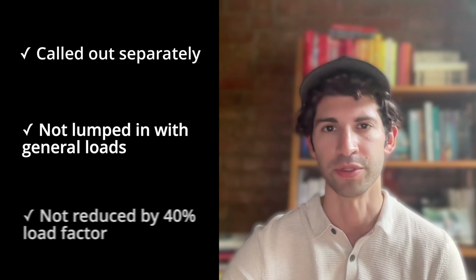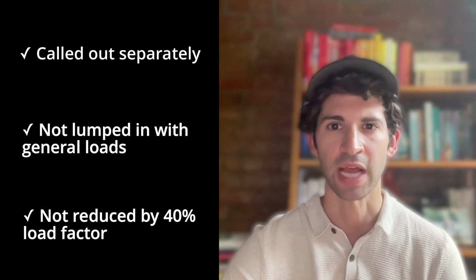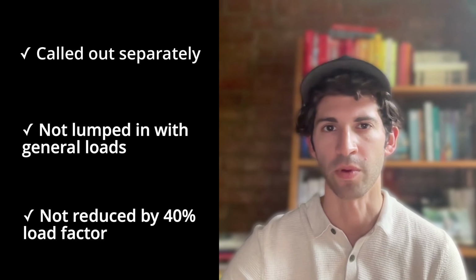Before we get into the numbers, let's talk about EV chargers and how to handle them in load calcs. This is an area that often causes confusion. Almost all AHJs expect that EV charger loads are called out separately, not lumped in with general loads, and not reduced by the 40% load factor. We've heard time and time again that most inspectors won't go for that.